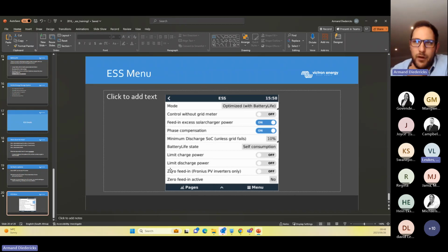So if you've got a scenario where a client's got an SMA or a different grid-tie inverter, it's not a Victron chain. You can install an energy meter onto the output of the PV inverter, and then just select it via that, and then just run exactly the same parameters that I just mentioned, and then it will still do frequency shift. So that's the abbreviation. It's frequency shift for AC coupled systems, to reduce the PV power when the power is not needed. So that reduces the dumping factor. So there won't be any dumping that causes issues via the inverters or the DC source.